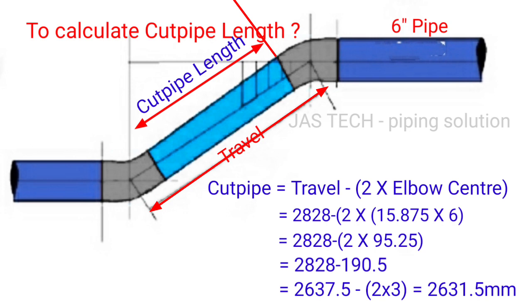Minus 2 times elbow center. This 45 degree elbow center, we know the formula is 15.875 times our sample pipe 6 inch. So 15.875 times 6 inch equals 95.25. So 2 times 95.25 equals 190.5 mm.